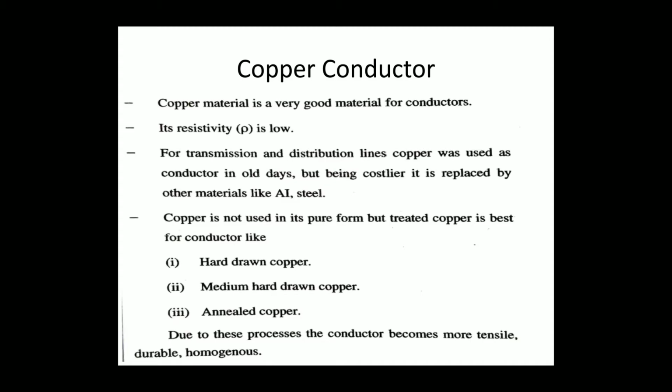Copper is not used in its pure form, but treated copper is the best for conductors, like hard drawn copper, medium drawn copper, then annealed copper. Due to this process, the conductor becomes more tensile, durable, and homogeneous.